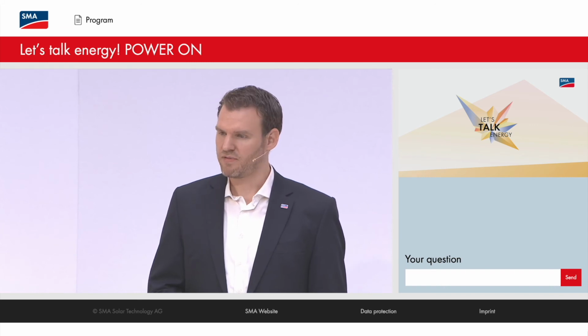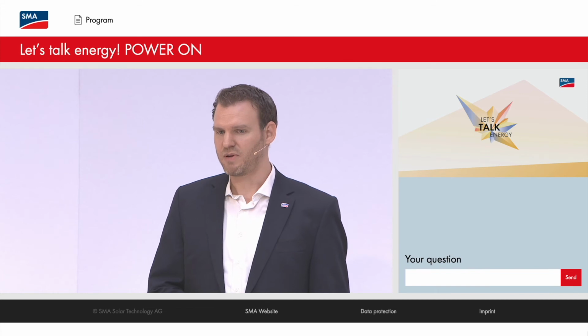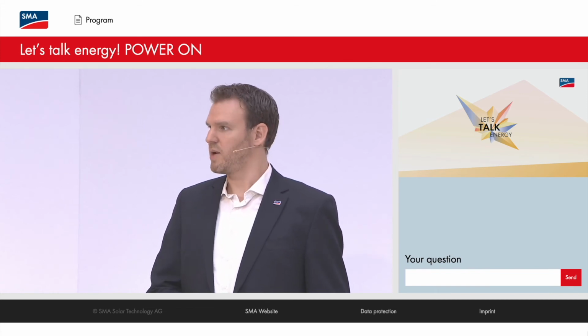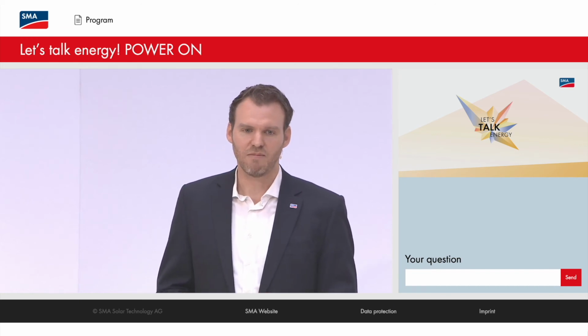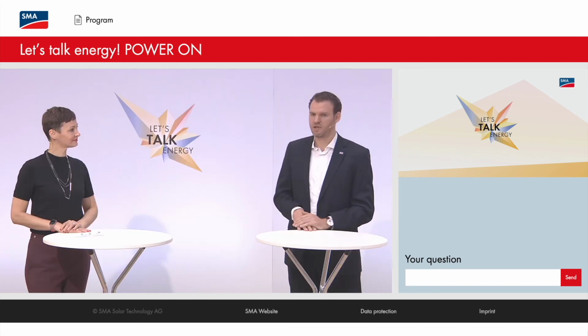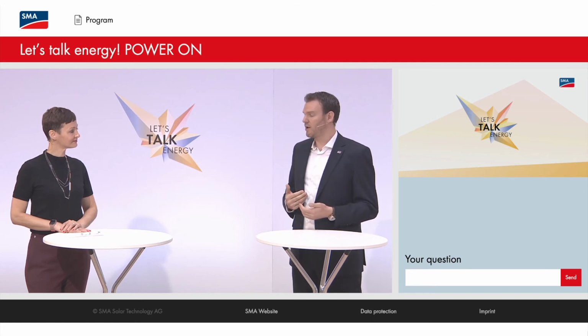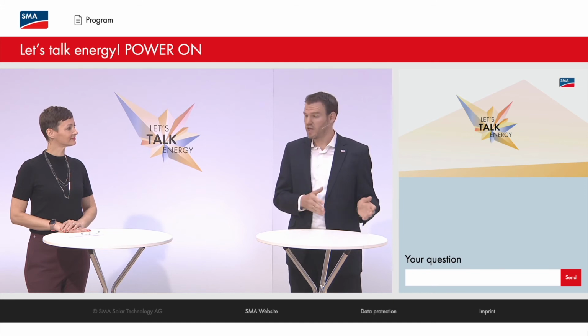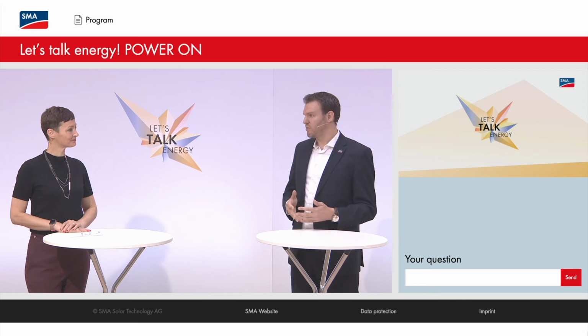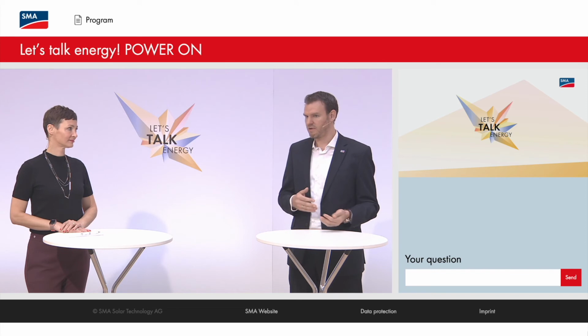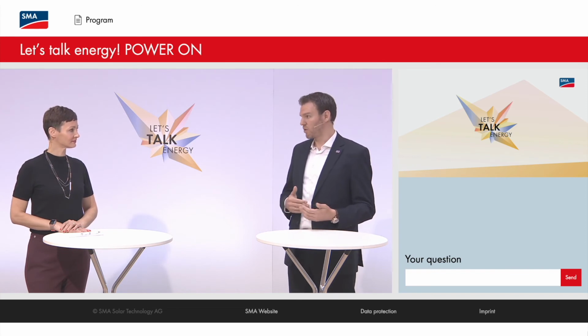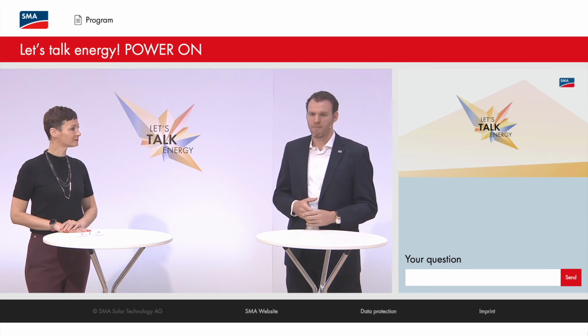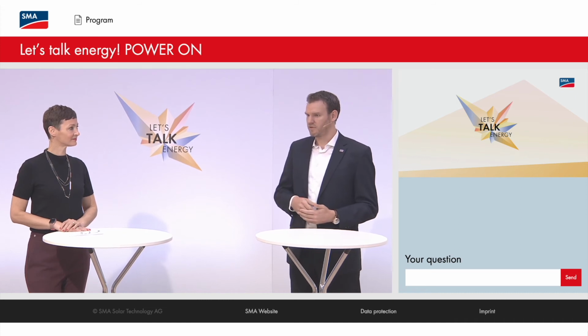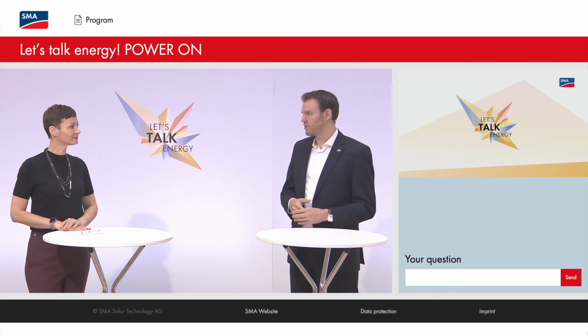That's a good one. We've seen a lot of inquiries, especially in new markets where utilities sometimes come up with interesting mandatory conditions, such as add some storage to stabilize my grid. So what does that actually mean? It's a very broad comment. Obviously something we've seen before is stabilizing frequency. Ideally, you can conduct a grid study to show before and after adding storage, so how the network actually improves. You can also shift energy from the noon peak to the evening. Grid forming is obviously extremely powerful, but the most complex topic by itself as well. If you're dealing with a utility not too familiar with this yet, it can be quite a long process. We can assist and help with dealing with the utilities—we have a team of product managers working with utilities. Frequency control, or avoiding irradiance peaks from rolling clouds, for example, can be a good argument for the utility, but it's difficult to quantify because it can be all or nothing.